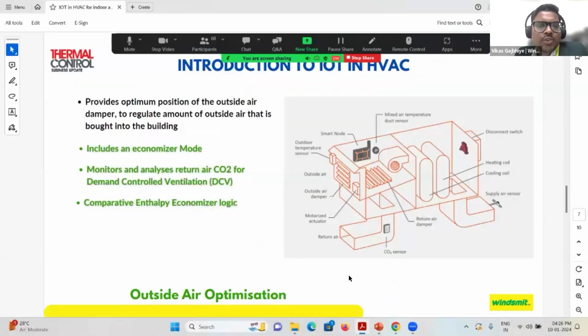Now we'll see the outside air optimization. Again, the outside air is very crucial and results in energy efficiency in the air handling units. It provides the optimal position of the outside air damper to regulate the amount of outside air that is brought into the building. The first point includes an economizer mode. What does economizer mode mean? The economizer mode will reduce or minimize the mechanical cooling on the basis of outside air temperature. Suppose the outside air temperature is lower than the ambient temperature, then at this time the mechanical cooling, the cooling valve of the cooling coil, will be closed and the outside air will be drawn inside to maintain the comfort level. That way we can save energy.